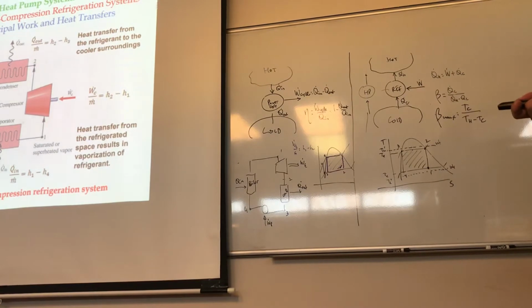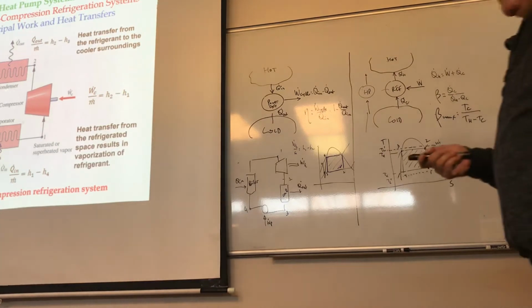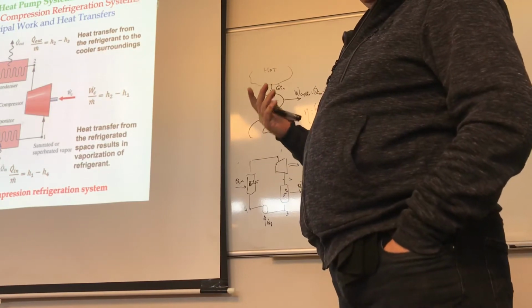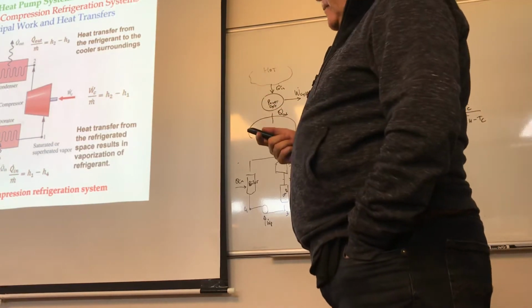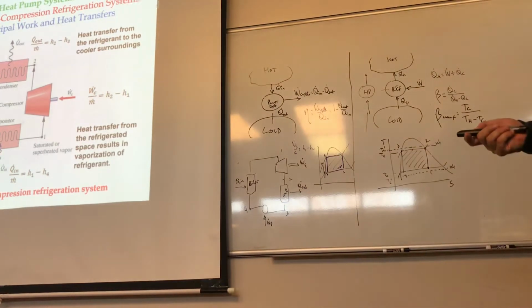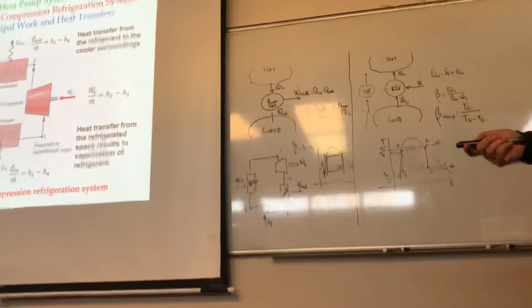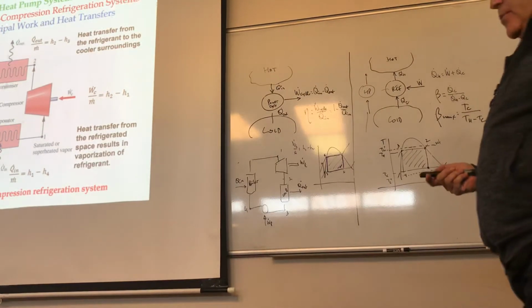Okay, one unit that you need to be familiar with, Q in, is the refrigeration capacity in kilowatts or BTUs per hour. Another unit is the ton of refrigeration that is used, I think, in the field or in the trade. A ton of refrigeration represents 211 kilojoules per minute or 200 BTUs per minute.